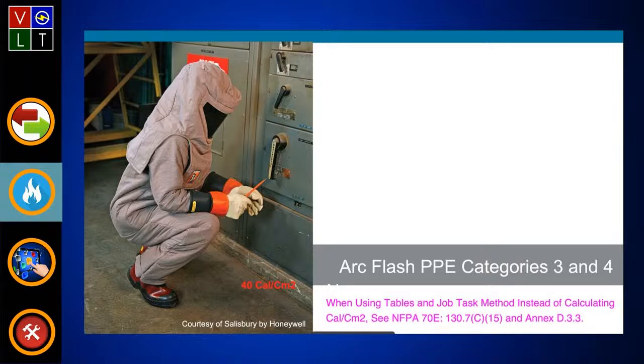Notice this guy's in a 40 cal category 4 type uniform, he's in a moon suit, and he's fixing to remove that device and rack it out, best I remember. Notice if you're 12 cal or less, you could just have a face shield, a balaclava, and dress as that, as we'll see. But if you're exceeding 12, you have to be in a moon suit, so you'd have to go to a category 4 for this particular task.